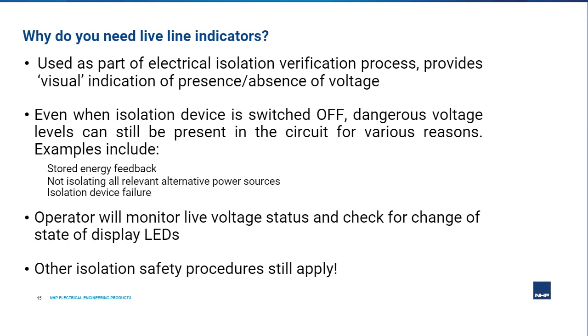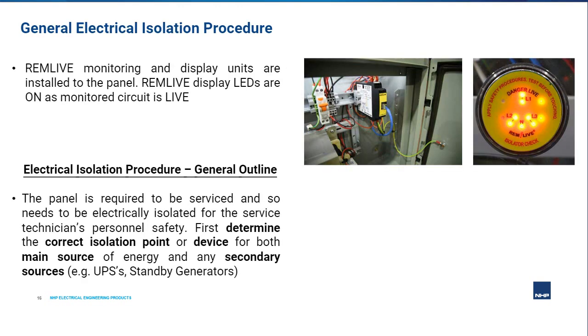Now, before the service technician assumes that correct isolation has occurred and they can work directly within the board, it's recommended that they test the circuits using a multimeter to ensure it has indeed been safely isolated before carrying on with the lockout and tagout process. Let's look at some of the general steps taken during the electrical isolation process and how the REMLIVE liveline indicator is used. This by all means is not meant to be a complete guide on the electrical isolation procedure, just a summary of the general steps so that we can understand the use of the REMLIVE liveline indicator a bit.